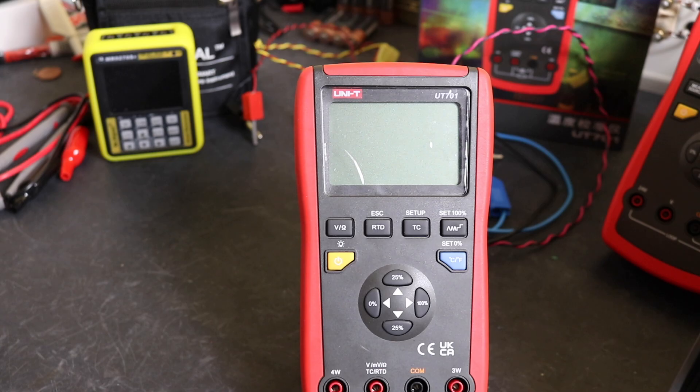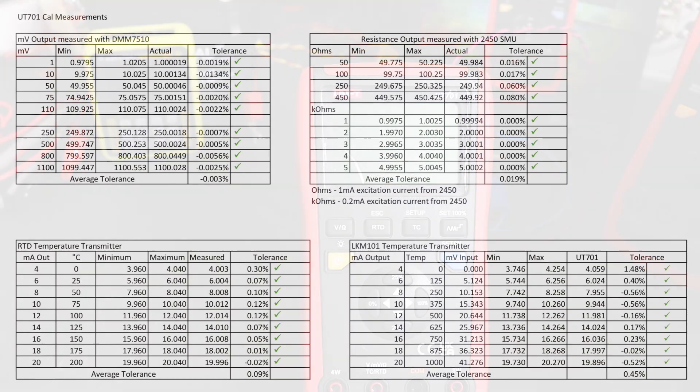Okay. So these are my test results here. In these tables, the values that you see here will be slightly different to the ones you see in the video because I waited for everything to warm up and come to temperature, including the transmitter, left everything powered up for an hour to let everything stabilize. So the results are slightly different in these tables. And on the top left there, we've got the millivolt output measured with the DMM 7510. Everything is just slightly low, but all within tolerance, ending up with an average tolerance of minus 0.003 percent. That's a good set of values there.